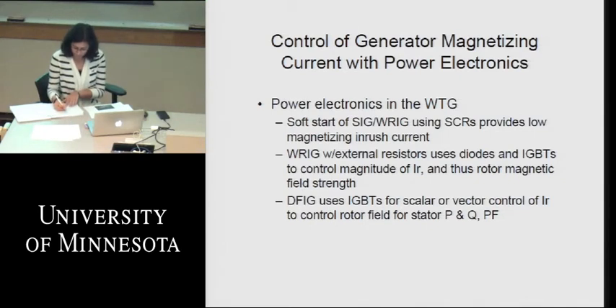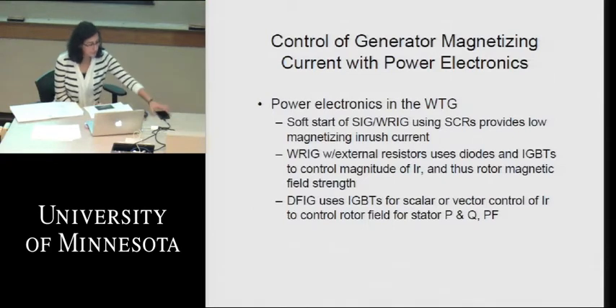But as I said earlier with the Type 2, these wound rotor induction generators using the external resistors, to control these resistors we've got the IGBTs and diodes to control the magnitude of the rotor current and thus the rotor magnetic field strength, and that way we can, again, control slip. On the Type 3 turbine, the DFIG, we use IGBTs, the insulated gate bipolar transistor, here for our voltage source converters for the rotor control, and we can either effect scalar or vector control by whether we're using a 2-quadrant or 4-quadrant type of arrangement on those converters. But we can control the rotor current to a very exacting level at that point, and again through Park's transformation we can effectively provide P and Q control independently, and we can completely control the power factor within the range of the design of the generator, much like a conventional generator.